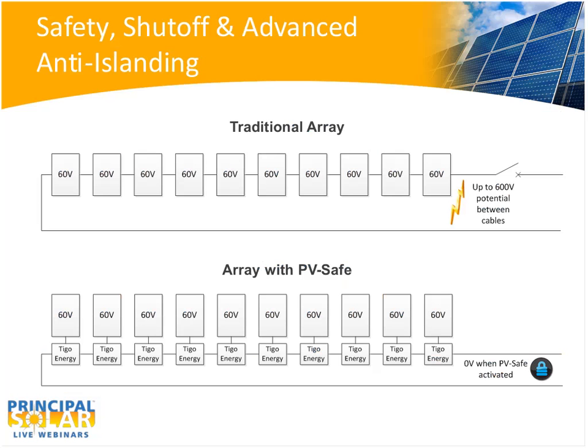Where that becomes a problem is if you've got a firefighter or maintenance workers, they could inadvertently make those conductors cross, and then suddenly you've got a burst of power that's waiting to happen, and those are lethal voltages. When you've got maximizers on the array, we're shutting off every single module. So if there are cables between each module and the Tigo maximizer, you may have 60 volts at that individual pair of cables, but that's a much more benign voltage than 600 volts.